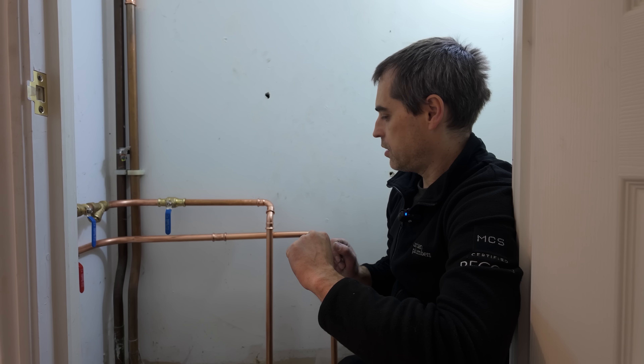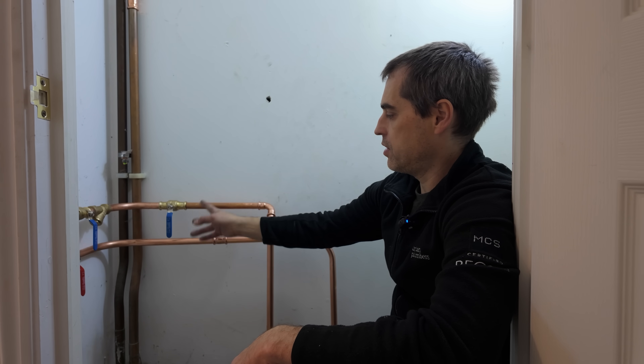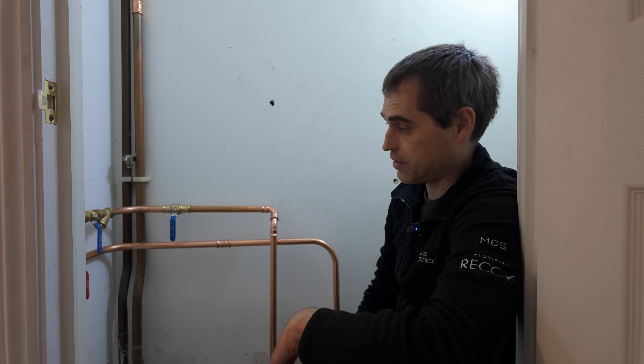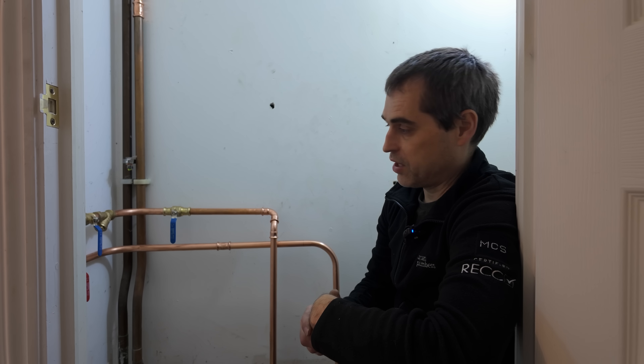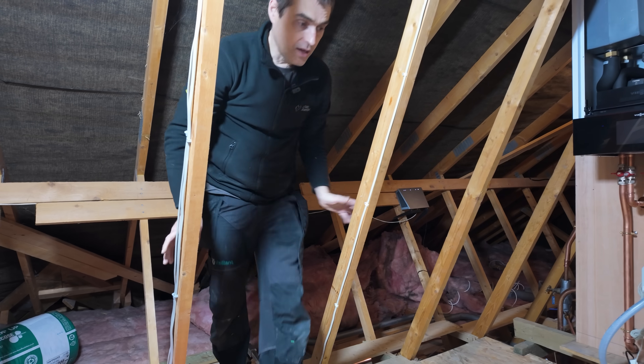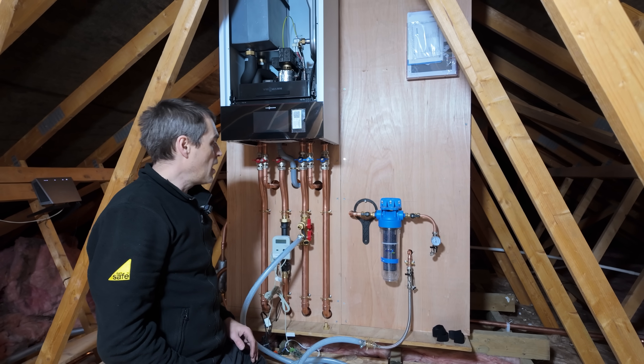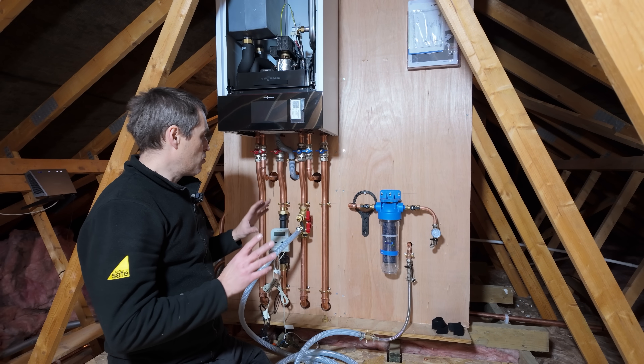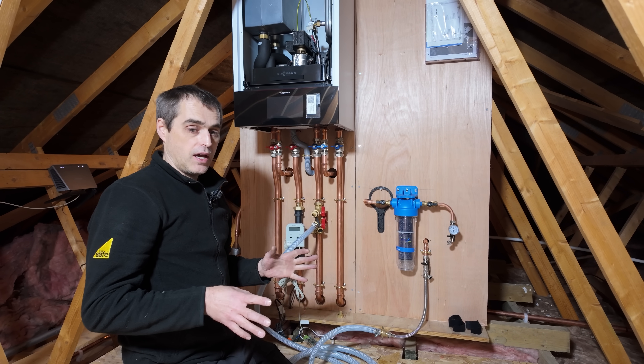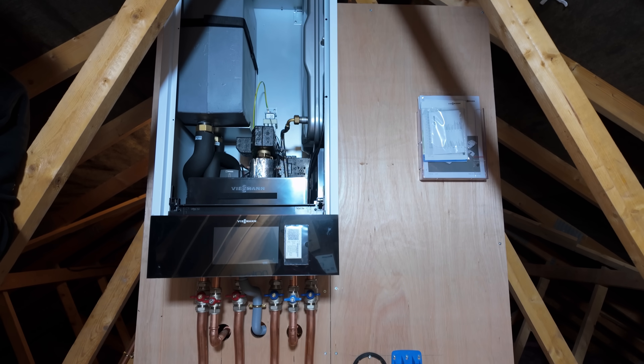The reason it's done this way is that in the very near future, the owner will install underfloor heating himself on the first floor. Once he's done it, he will cut those two pipes and put his manifold on this wall. I've got another white strainer because we will flush the rads, but I want to keep the rads with another strainer to make sure the old open-vent pipes or rads are not going to contaminate the new system too much. In here we are ready to start pressure testing the system. We've bypassed the filter unit because we don't want to use resin for no reason, and I'm going to leave Marie on site tomorrow to flush the system, demineralise the water, and insulate all the pipework, while the electrician wires the whole setup.